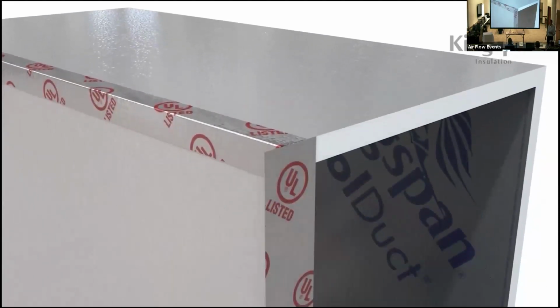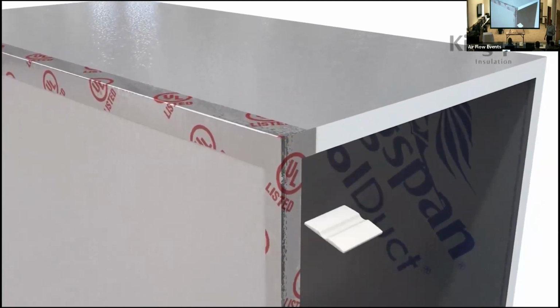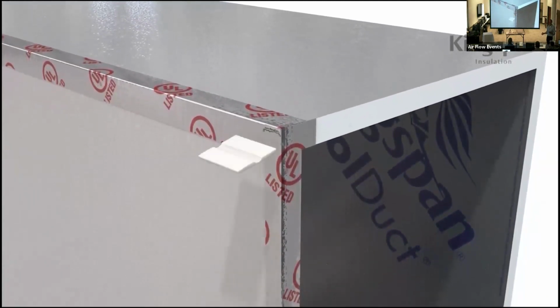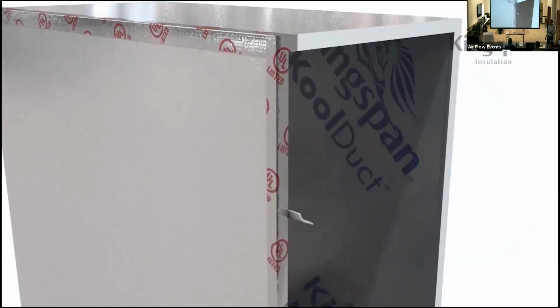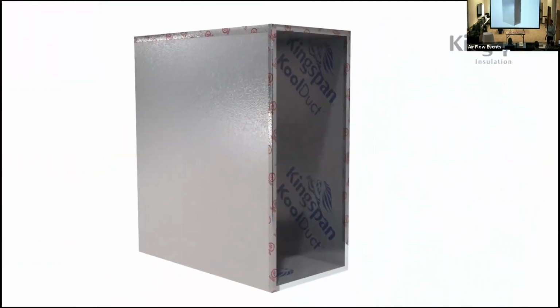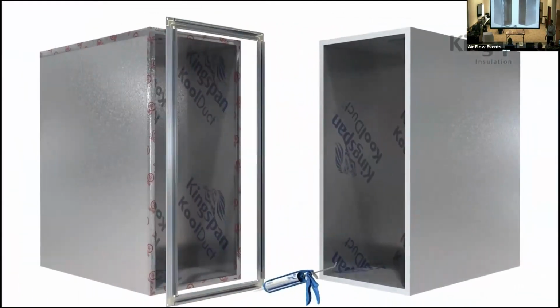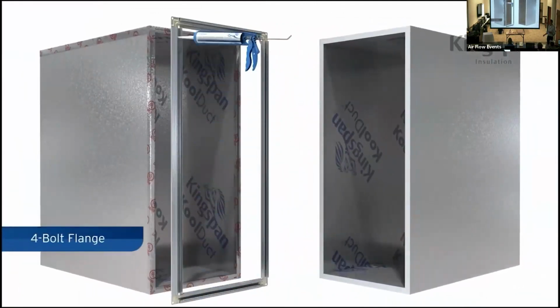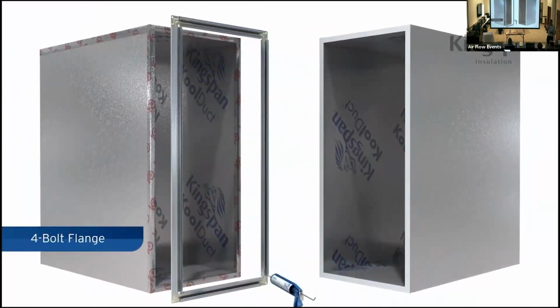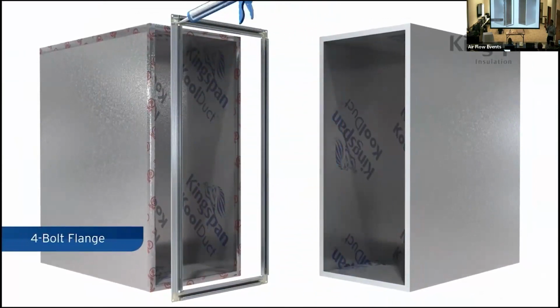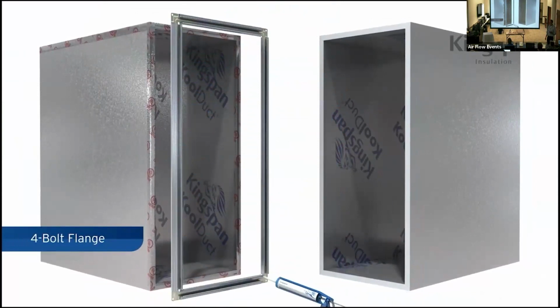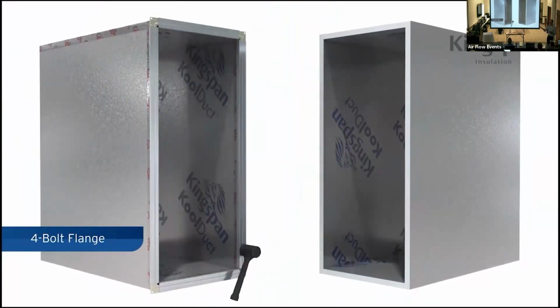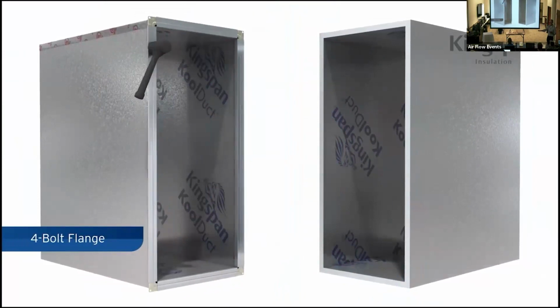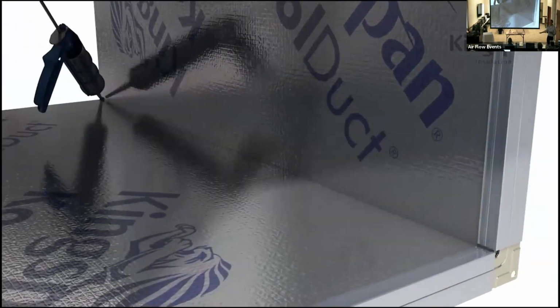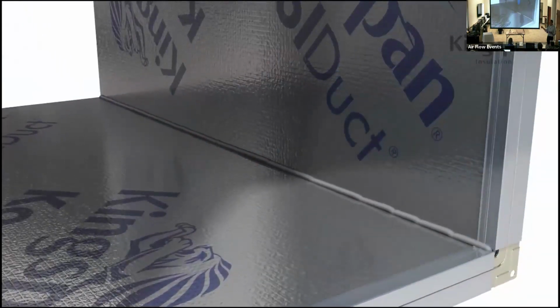You gotta tape all the open sides because you don't want the phenolic exposed to the duct. I don't think there's anything wrong with phenolic, but you just don't want it in there. A little squeegee goes all the way around. And then this frame, notice that the frame is built so it sits on both sides of that insulated panel. But when it gets to the field, it looks exactly the same as what the contractor is already familiar with. It's the same 4-bolt flange that they're comfortable with. Even though we've got all this material, we still seal the joints.